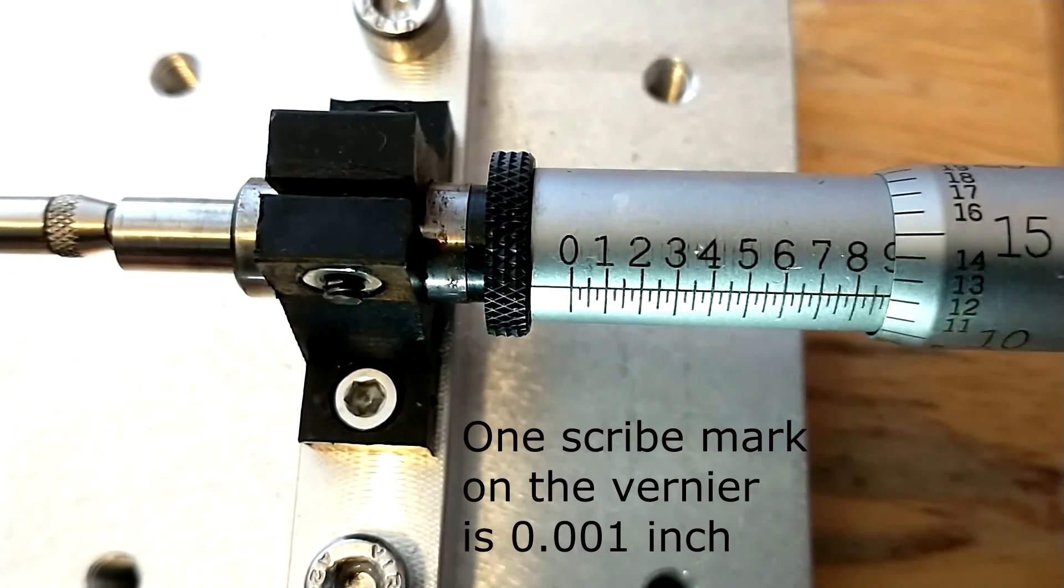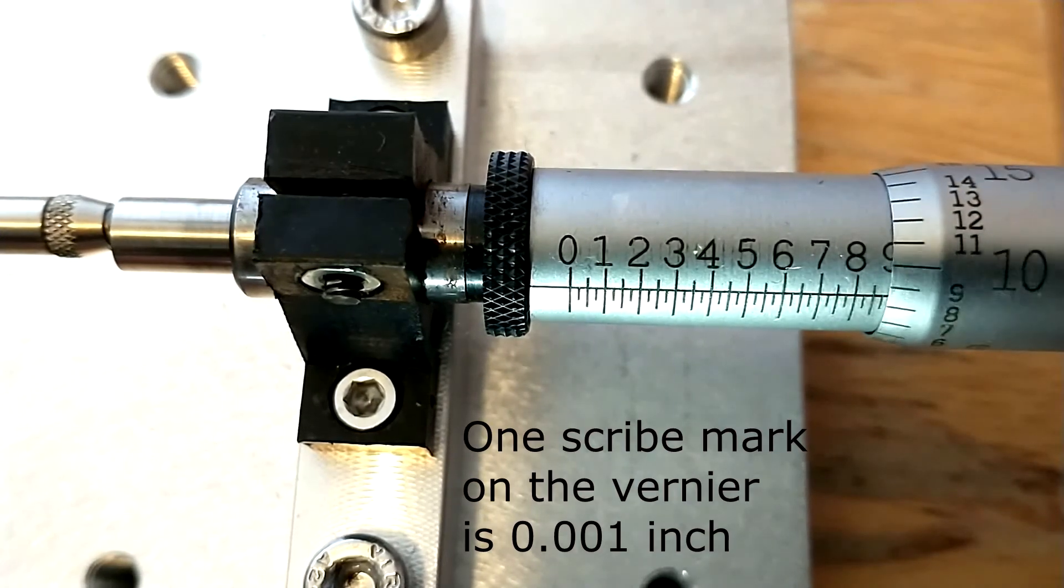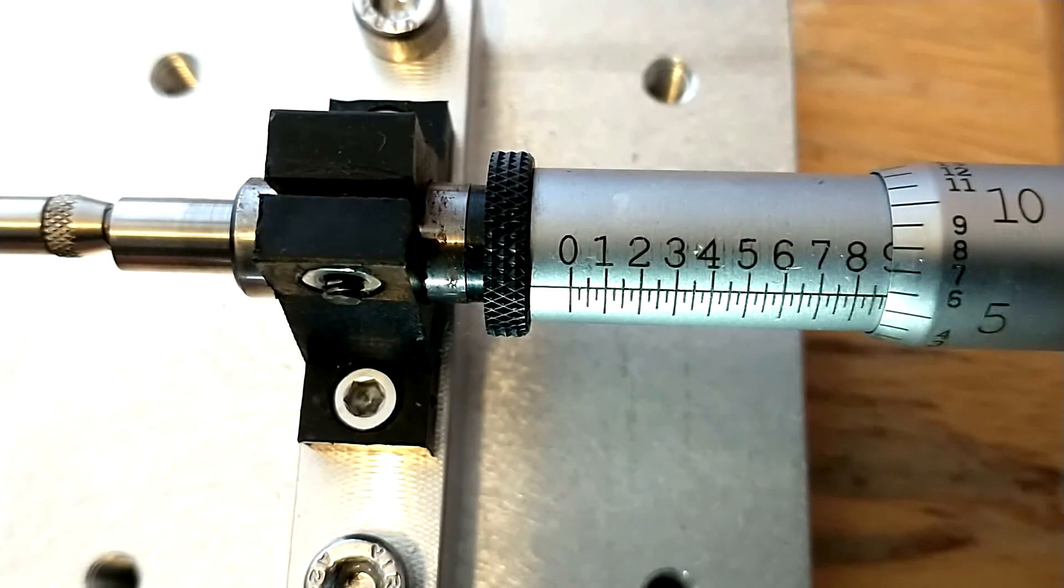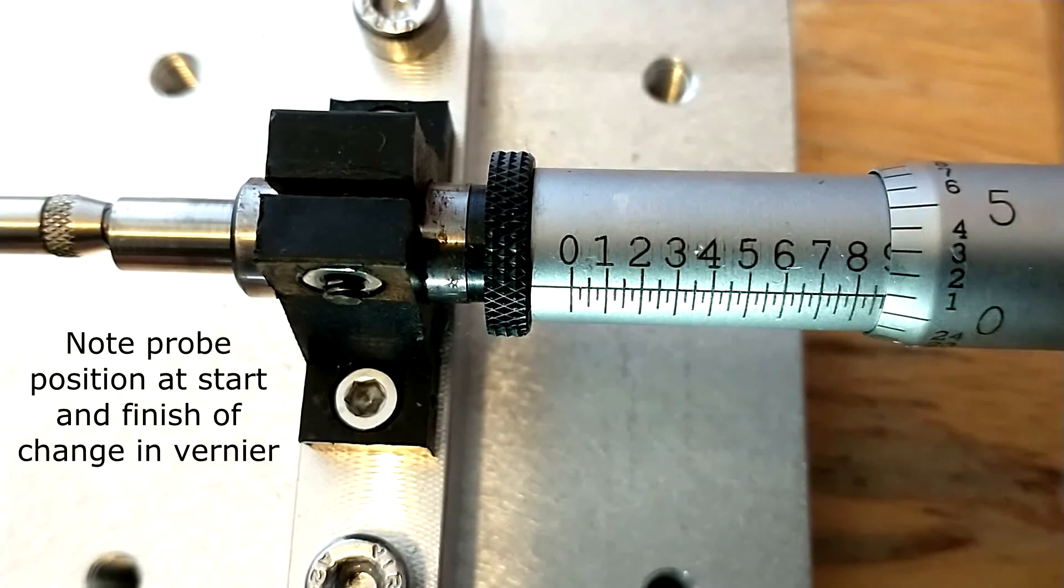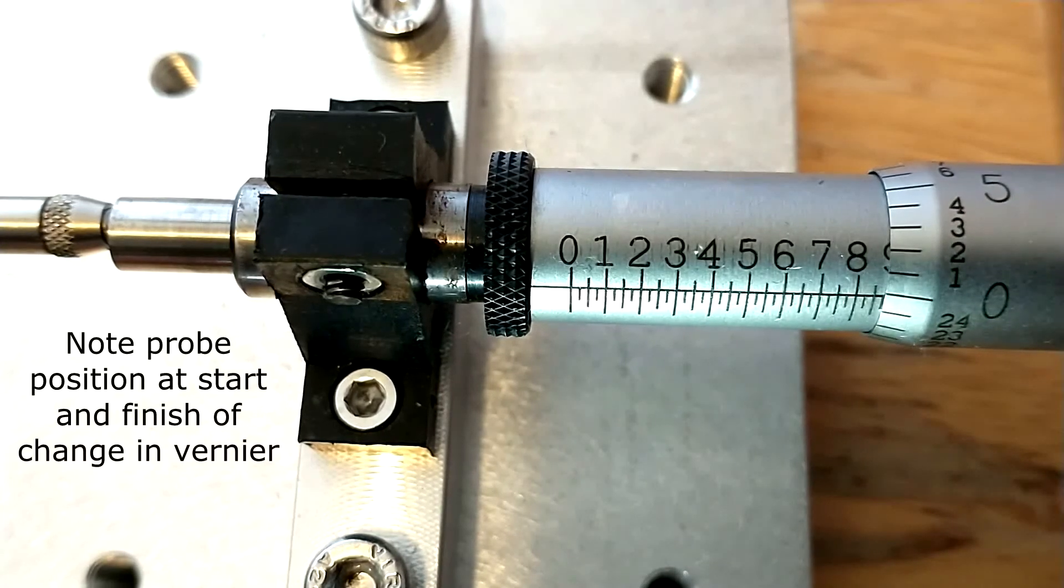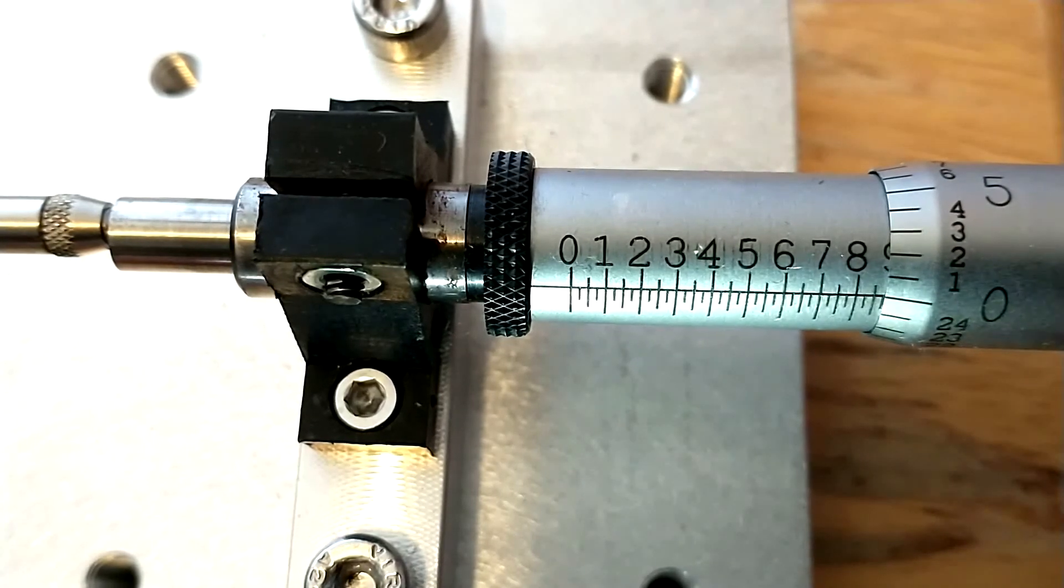I'm going to advance it, and each one of these scribe marks on the vernier represents a thousandth of an inch. I'm going to advance that to that location. I've just advanced 0.025 inch.